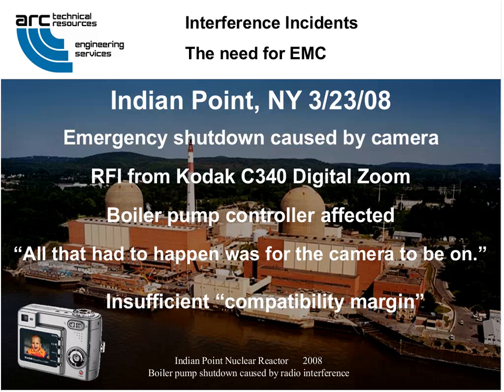More stringent specifications of the control equipment was clearly called for in this incident, since normal operation of a nuclear plant was susceptible to upset by nearby consumer electronics. This indicates an insufficient compatibility margin between the emissions levels from the cameras or other devices at close range and the susceptibility thresholds of the controls and their wiring in the cabinets. If that difference is as high as 10 dB, then your system is probably pretty reliable. If that difference is down to a few dB, your system's on the edge of failure all the time. And that's what happened here.